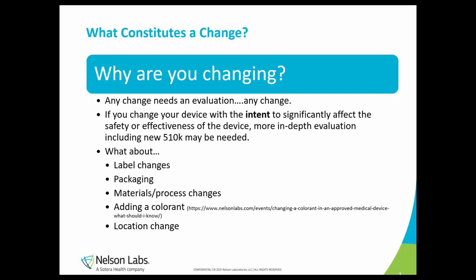And then you go into the regulatory aspect. I just have something here from the FDA as far as intent, which I think is important to understand: what the intent of this change is. They mentioned that if it significantly affects the safety or effectiveness of the device, then you need more in-depth evaluation, including maybe a new 510(k). For me, intent is a big important word when you start looking at changes, and it needs to be recorded why you're making these changes and the risks to the patient, and then any steps you took to mitigate those risks if you identify them.